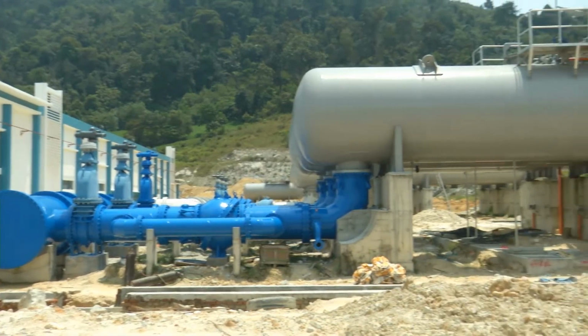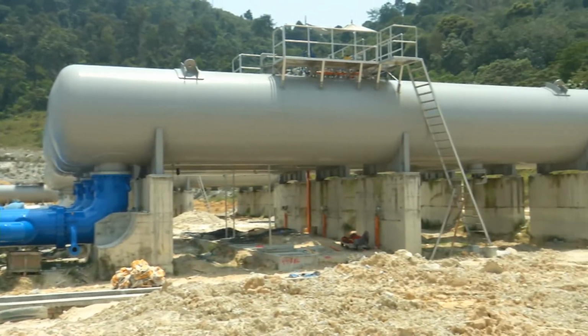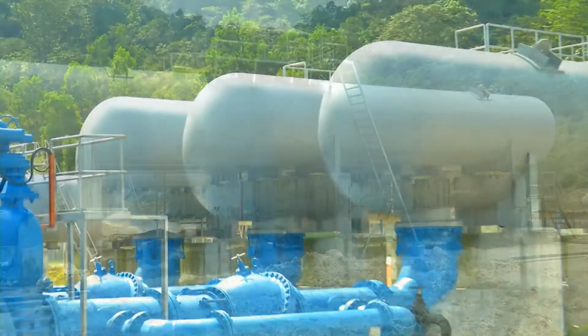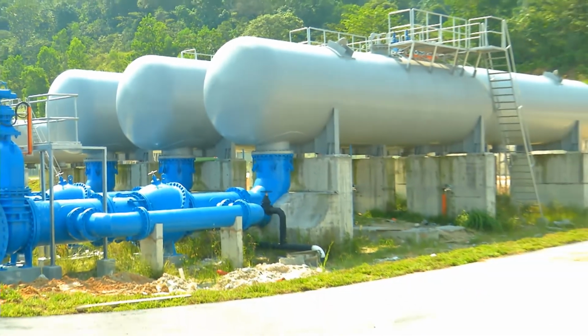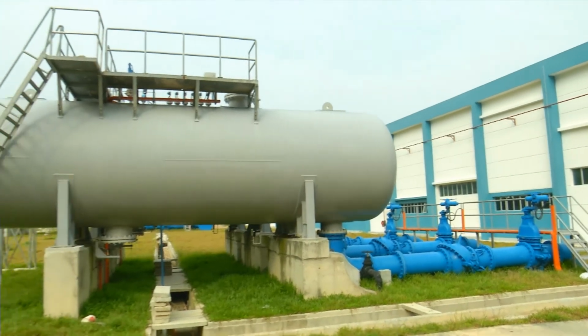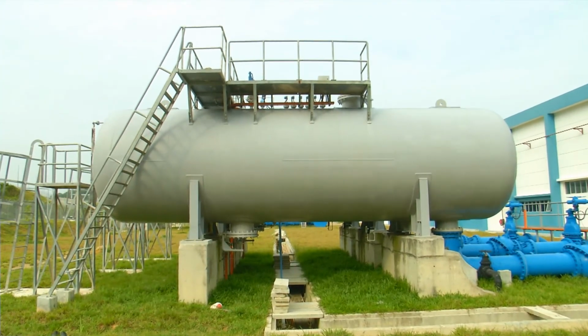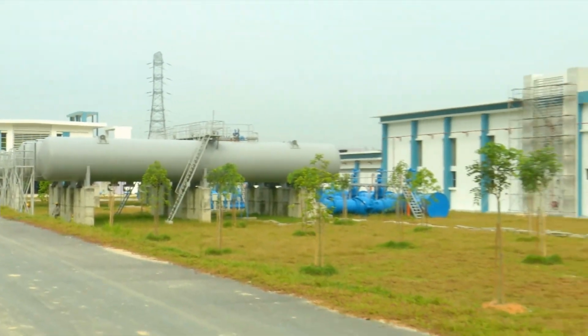Surge tanks are installed to relieve excess pressure caused by water hammer, and to provide a supply of water which reduces negative pressure if a valve is suddenly opened. The large increase in pressure can cause pipes to crack and in some cases burst.